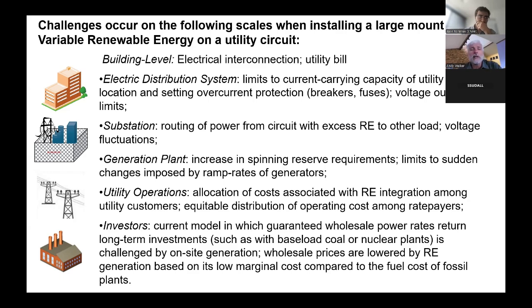These are things that affect the local line to the distributed generation facility. And then back at the substation, we have to think about routing power from circuits that have extra renewable energy generation to other circuits that can use that. A typical off-the-shelf radial substation bus configuration would do that, but a lot of substations have ring buses and network protectors that can prevent a backflow of electric power, so there might need to be changes to the configuration of the substation.